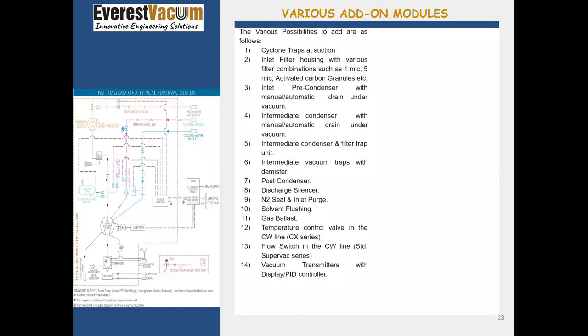So these are the modules that I was discussing in the last slide. This is also mentioned in our standard catalogs. This is a typical P&I diagram on the left, and these are the various additional modules that can come into the loop. The various possibilities to add on are cyclone traps to trap any particles prior to their entrance into the pump. Then there could be inlet filter housings depending upon the micron ratings. It could be either 1 micron or 5 microns, so it depends what kind of process we are in and what the particle sizes are that will enter our pump.